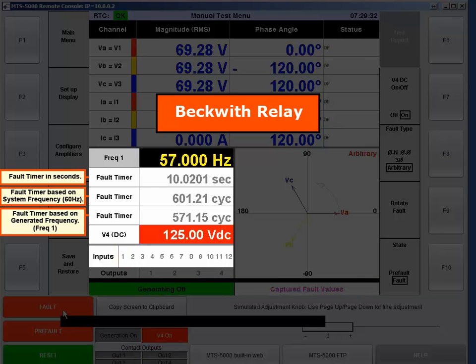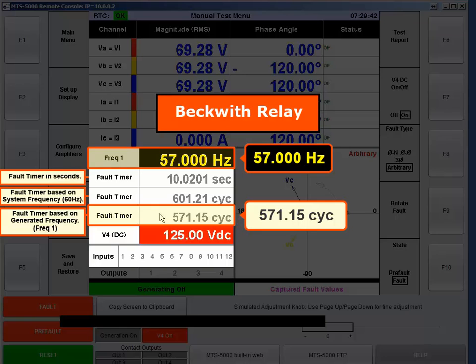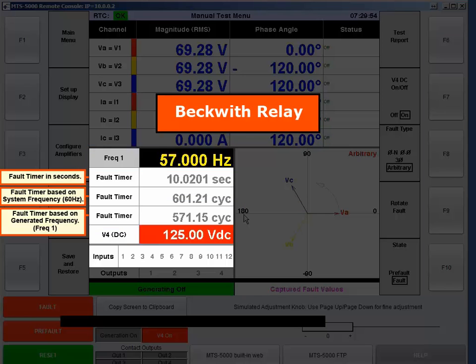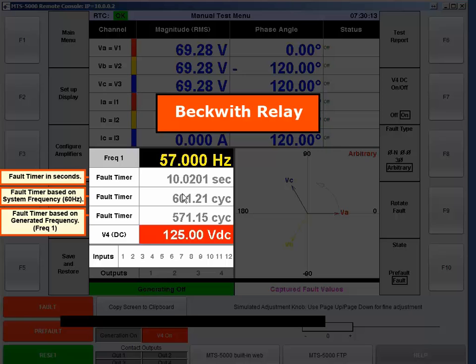Let's hit fault and wait 10 seconds. The trip came in, which again is 10 seconds or 600 cycles based on 60 Hz, and 571 cycles based on 57 Hz. This test set's default timer is the bottom one — the 571.15-cycle timer — which could be a problem. The 601.21-cycle timer never existed in this test set's history, and that was a problem for me one day when testing a Beckwith relay. I requested they add that second timer, and that's what I got.